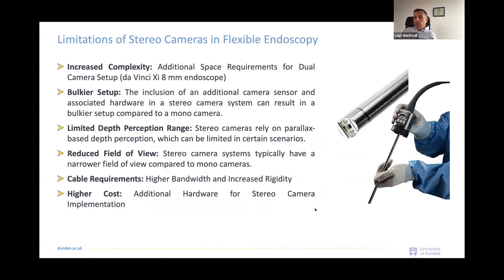And in surgery, the field of view is close to 60 to 70 degrees, while in flexible endoscopy, you need up to 180 degrees, so a completely different lens for the camera. Then a stereo camera requires higher bandwidth, increasing the rigidity of the cable. In the case of a tethered device, this will increase the tether drag, and also the cost because you need to deploy additional hardware and make the device bigger. So this solution works very well for pure surgery. However, for flexible endoscopy, it's difficult to deploy.